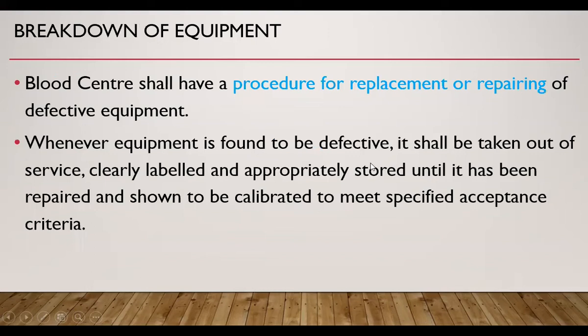Whenever equipment is found to be defective, it shall be taken out of service, clearly labeled and appropriately stored until it has been repaired and shown to be calibrated to meet specified acceptance criteria.